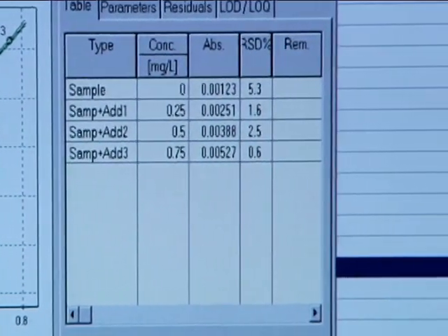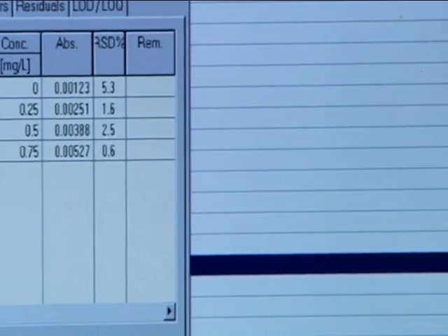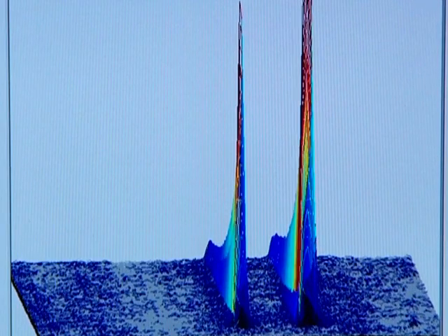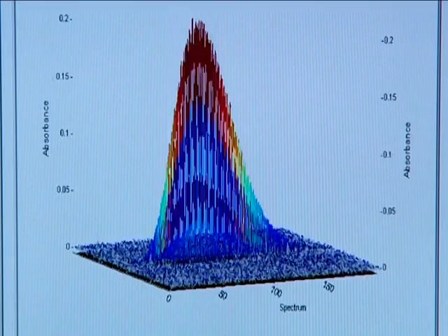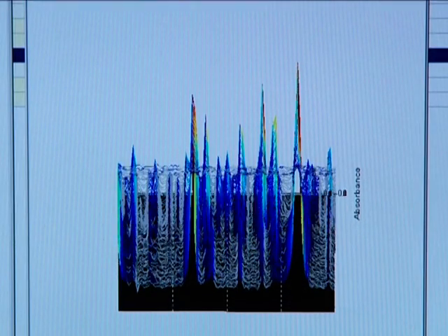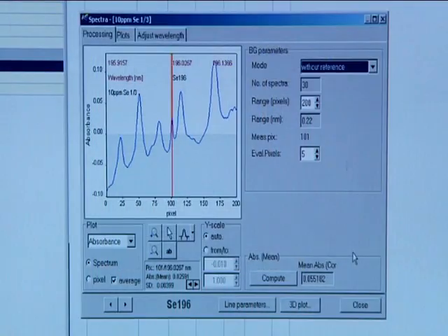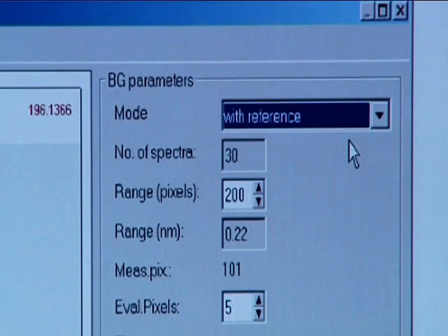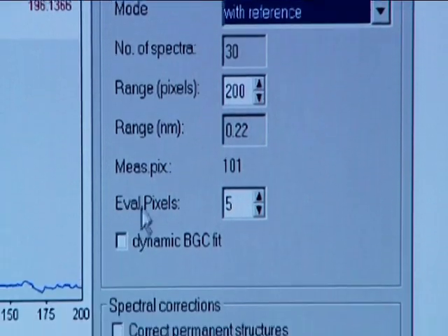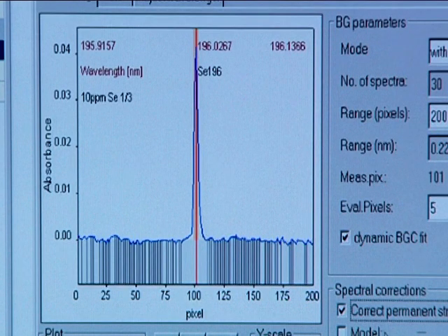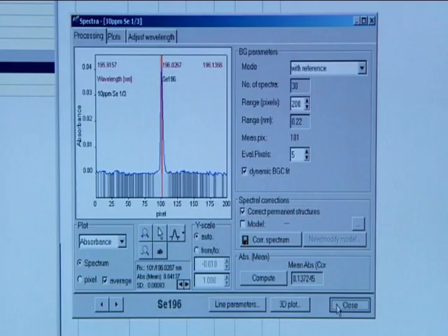The signal-to-noise ratio, clearly improved in this way, also enables the smallest signals to be measured. In contrast to a classical AAS technique, for which total and background absorption are measured alternately, background correction of the ContraAA takes place simultaneously. Because the whole spectrum is recorded, the spectral background is now visible. Spectral structures such as molecule bands or element interference are recognized automatically and taken into consideration by the correction.